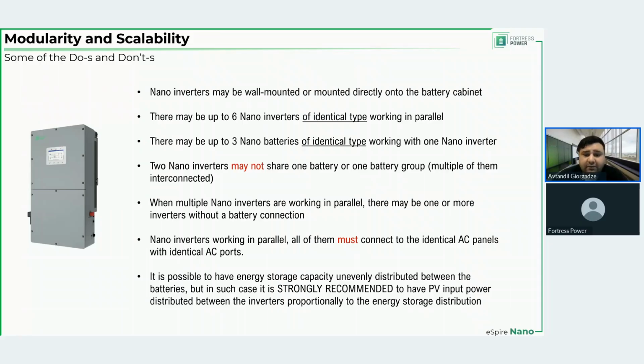Because if you have a generator present and connected to the nano inverters with the batteries, right? Those don't have ports available for the AC coupled PV. It's either or. Those smart ports are used either for AC coupled PV, generator, or smart load. You cannot interchange, or you cannot have both of them connecting at the same time. So if the generator is already occupying the smart ports on the inverters with batteries, right, the ones that you're probably using for backup, in that case, you cannot connect AC coupled PV to those, but you can connect additional PV to the additional nano inverter that has no batteries to it.